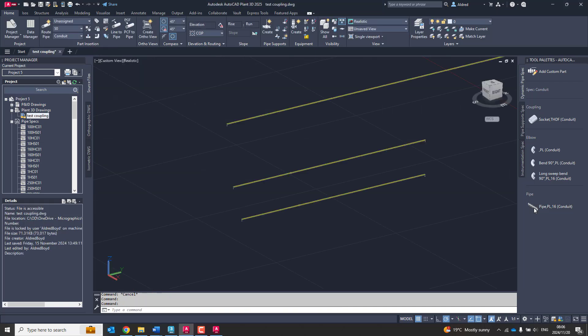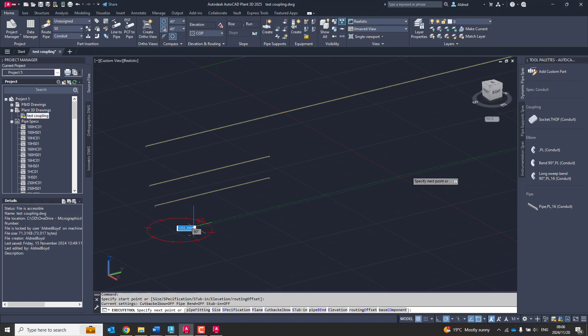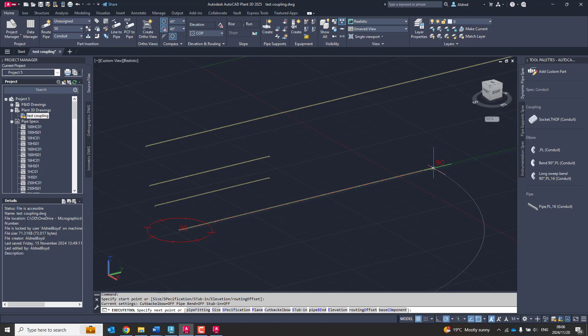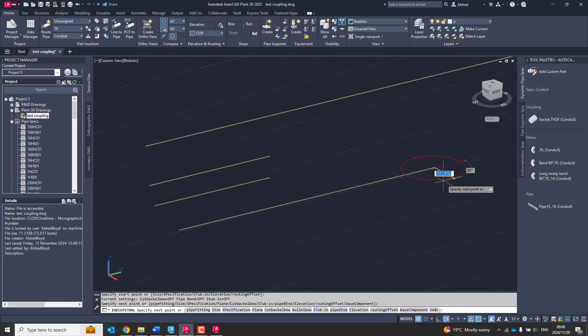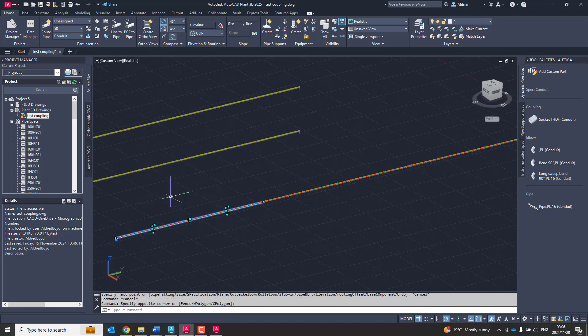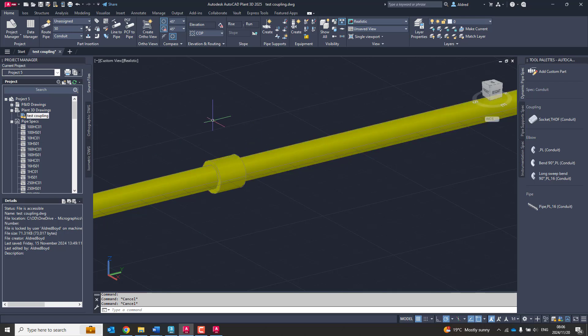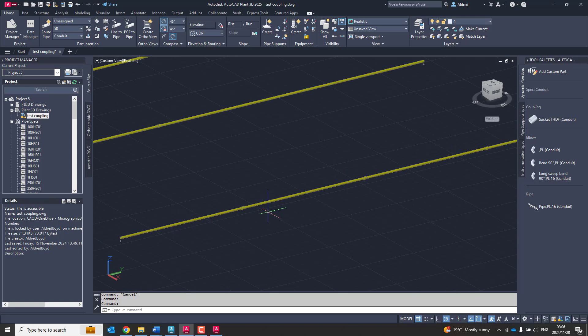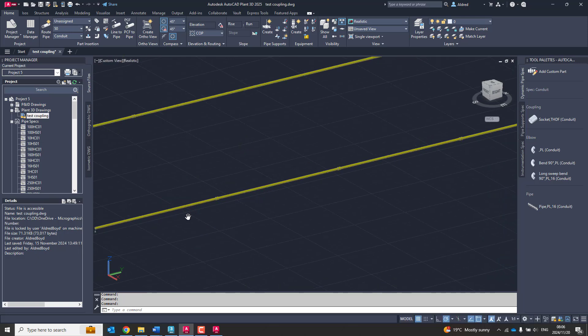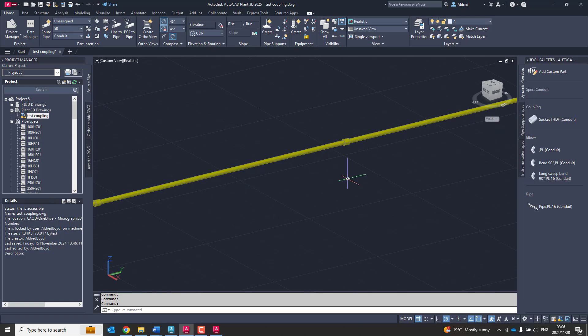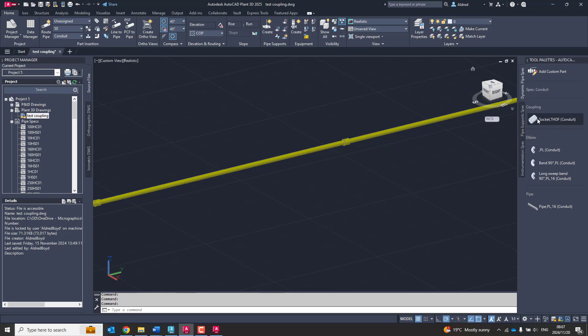So let's go to Pipe, run the pipe, and if I go and select that, you'll notice it's putting the coupling in. So what we've done over here, we've created a conduit of sorts at a fixed length, 3,000, and what we did, we went into our compound joints, and we made sure that the compound joint was set up correctly so that we could go and grab that coupling over there, and then we just modified the simple joint so that it automates the coupling instead of me having to go into each one and then substituting out each joint for the coupling.